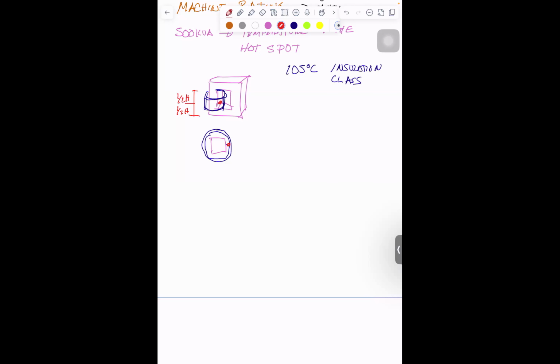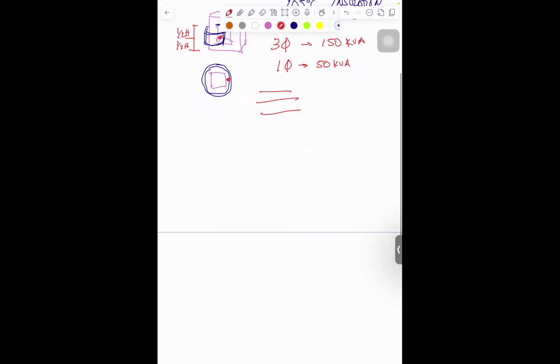We rate a device, let's say a 3-phase device rated for 150 kVA. Whatever the device is, a generator, a transformer, a motor, you name it. What this really means is single phase is 50 kVA, because you can't put the entire load on a single phase. So I can't say this single phase machine is 150 kVA, but a 3-phase machine can be called 150 kVA. This assumes balanced operation.